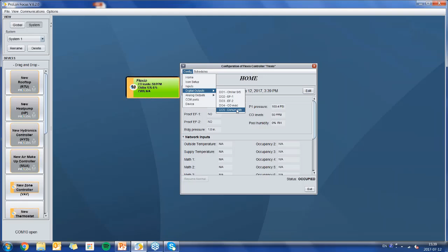When I do that and go back onto my FlexIO controller, I can go into any given output. Let's say I go onto this output and change it so it goes based on slot number 4. So now this specific exhaust fan is going to be controlled from the schedule coming from the network controller. That means we could technically have 8 different schedules controlling 8 different outputs, nothing stopping us from controlling 8 different exhaust fans or lighting controls as well. Plus, when you add that with the contact inputs, it means we can find out whether things are on or off and so on.